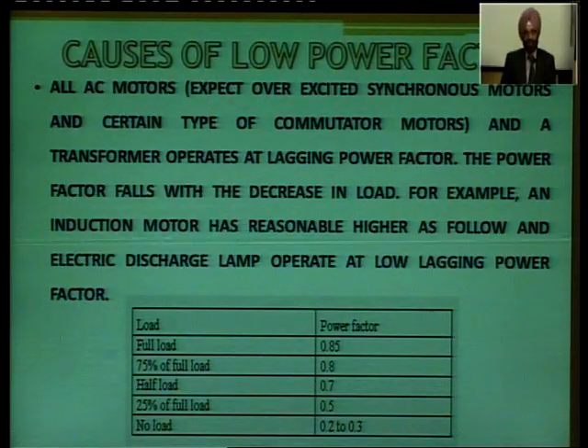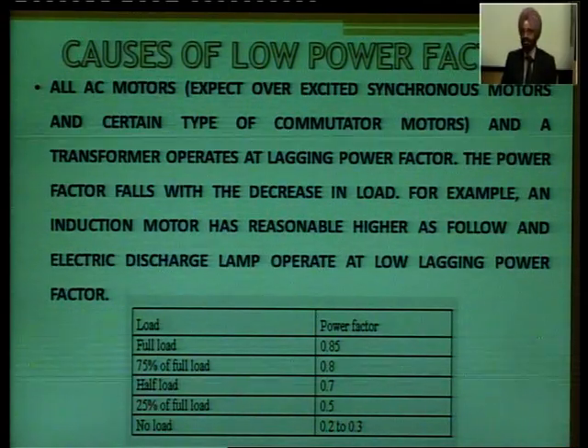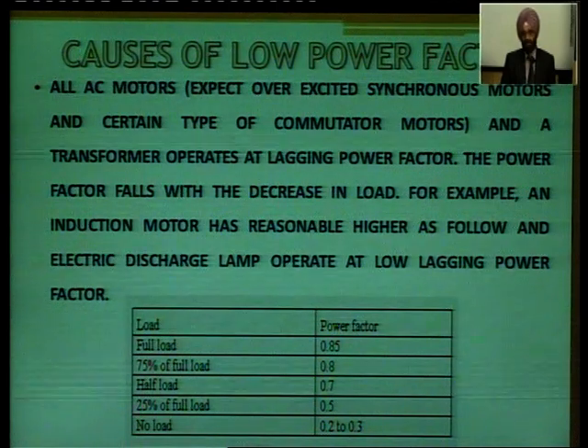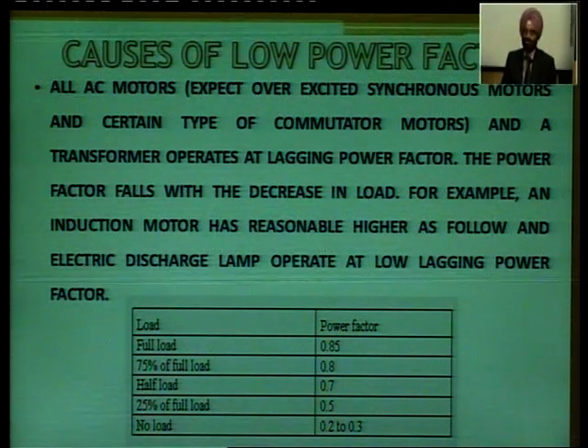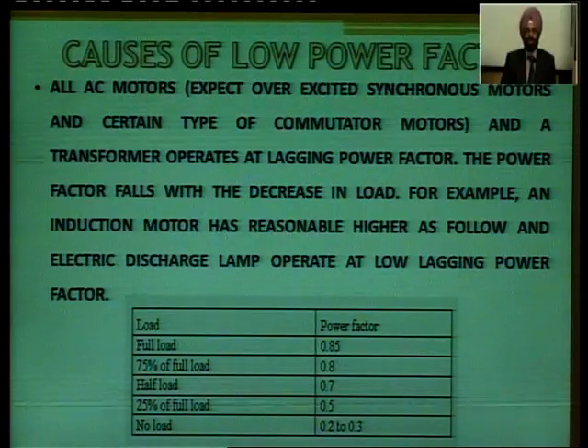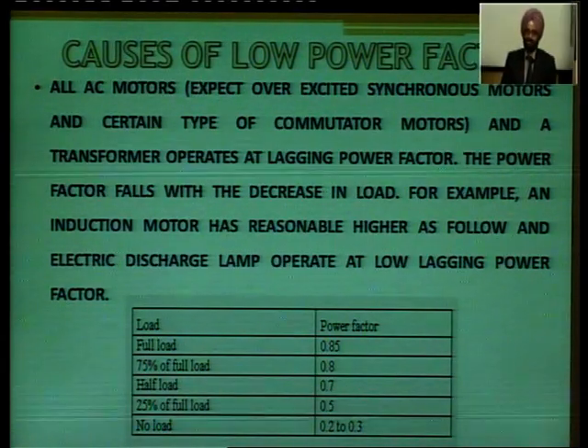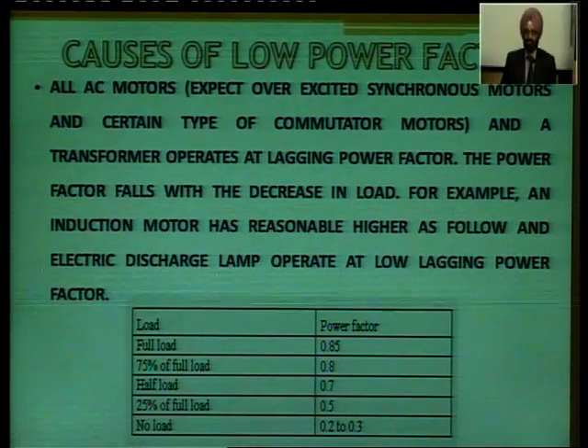So at full load the motor draws more real power but less magnetizing current. Magnetizing current does not change from no load to full load, but the real power changes from no load to full load. So the power factor goes on improving from no load to full load. So always try to run your machinery at higher loads, at fully loaded machines.